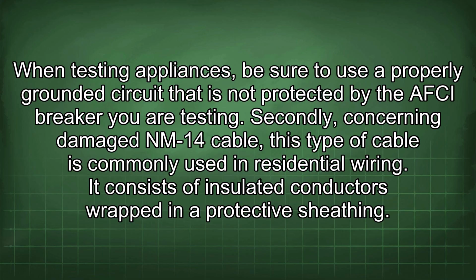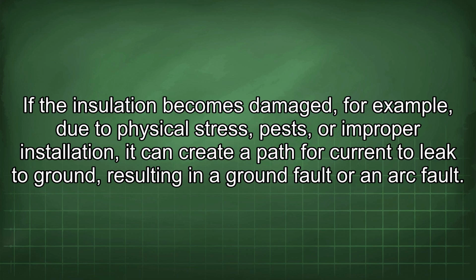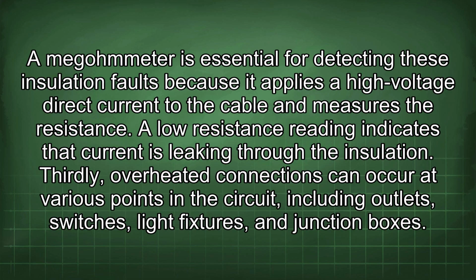Secondly, concerning damaged NM-14 cable, this type of cable is commonly used in residential wiring. It consists of insulated conductors wrapped in a protective sheathing. If the insulation becomes damaged, for example, due to physical stress, pests, or improper installation, it can create a path for current to leak to ground, resulting in a ground fault or an arc fault. A megohmmeter is essential for detecting these insulation faults because it applies a high voltage direct current to the cable and measures the resistance. A low resistance reading indicates that current is leaking through the insulation.